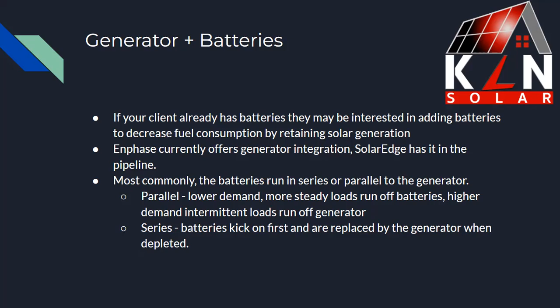When you put them in series, the battery kicks on first and takes all the loads that are set to be backed up. Then, if and when it gets depleted, it's replaced by the generator. The following day, the sun comes back out and it's able to re-engage and recharge.